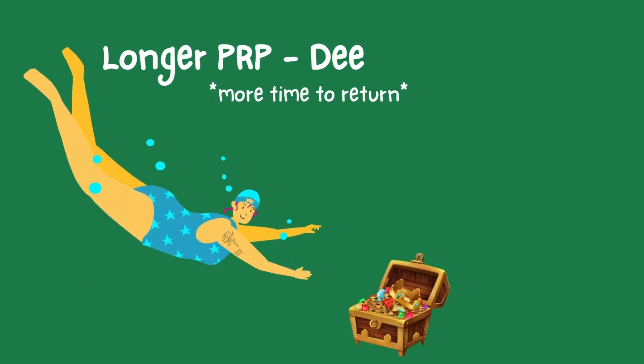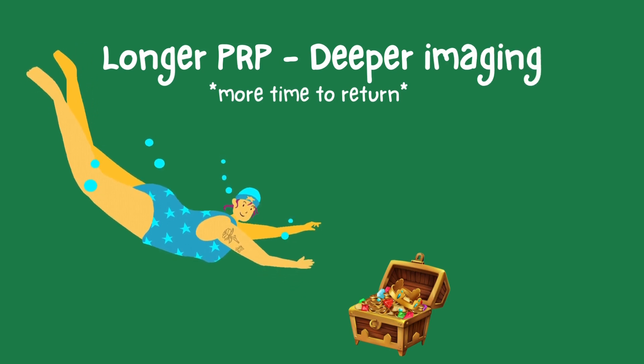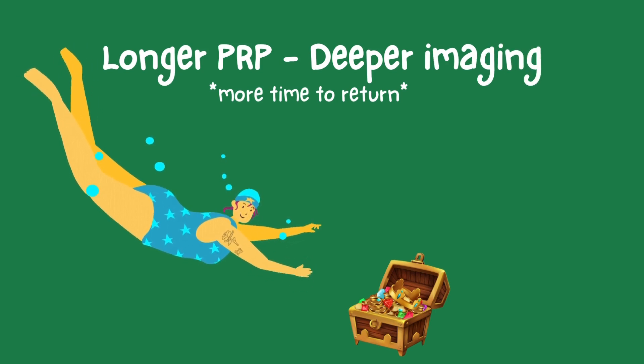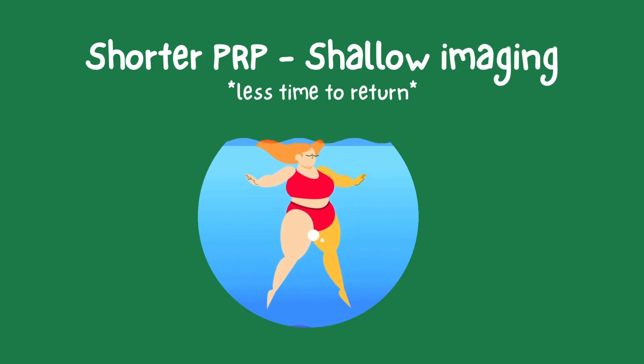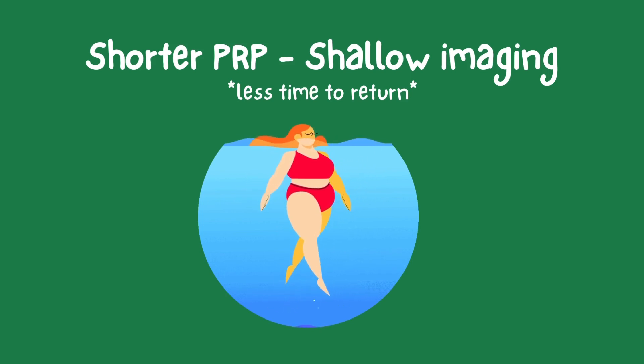PRP is directly related to the depth of imaging. When imaging deep, the PRP is long, and when imaging shallow, the PRP is short. Think of it like this: when you're diving deep into imaging, searching for structures deep in the body, you need more time to wait for echoes to return from those distant depths — more time means a longer PRP. But when you're just skimming the surface, capturing images of shallow structures near the skin, you can quicken the pace — less depth means less time for echoes to return, meaning a shorter PRP.